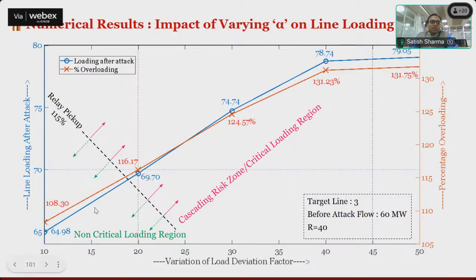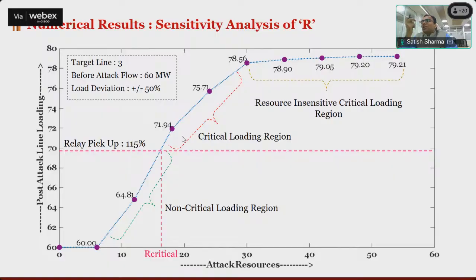Below this is the non-critical region. If the load variation is below 20%, it will not create a cascading effect or line overloading. But if the variations are more than 20%, then it's a critical loading region. In this case the line will have more than 115% of the actual loading, and it will trip, and if it trips, it leads to cascading failure. This is how we can analyze it. For a different test system, it will be different; it's not always that 20% variation holds for all systems. But a system operator can do some analytics and find out how much deviation is fine, and based upon that we can identify how much error can be considered from the state estimation or bad data detection.